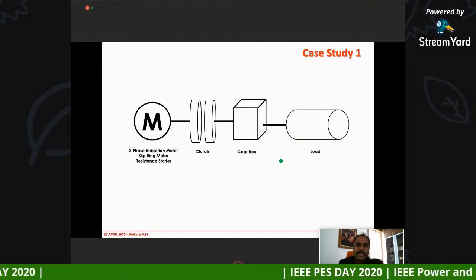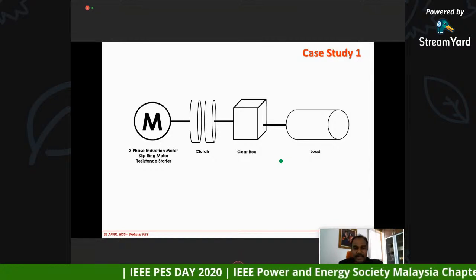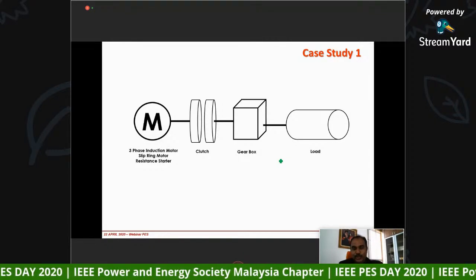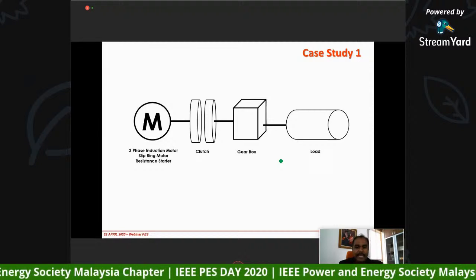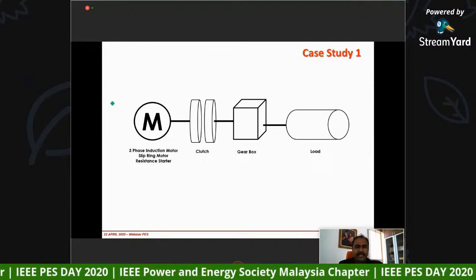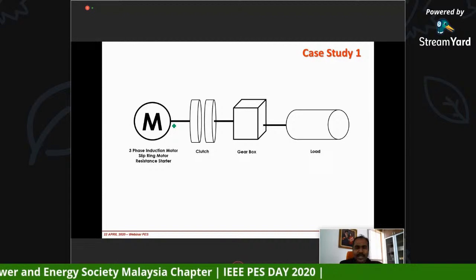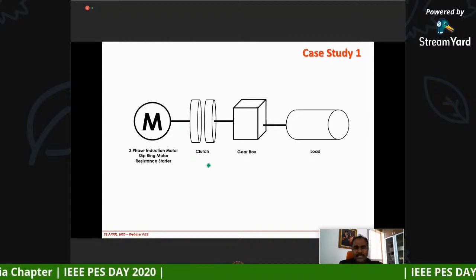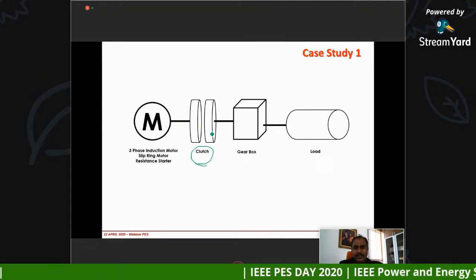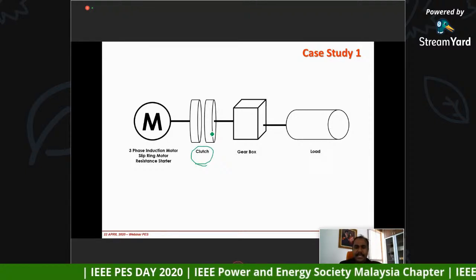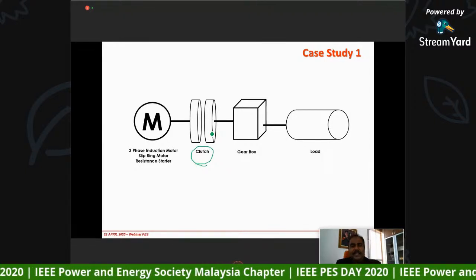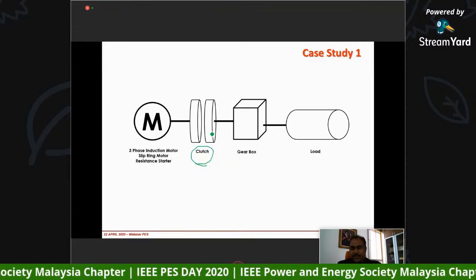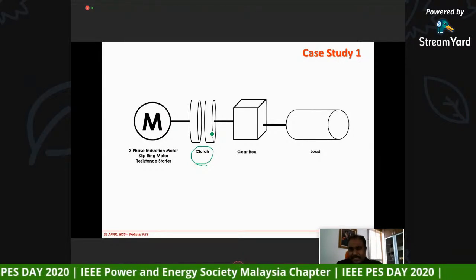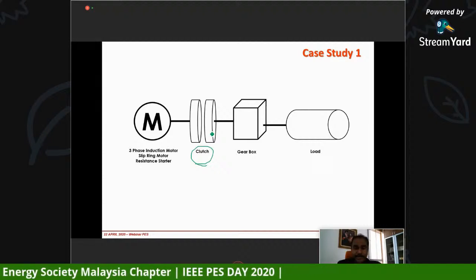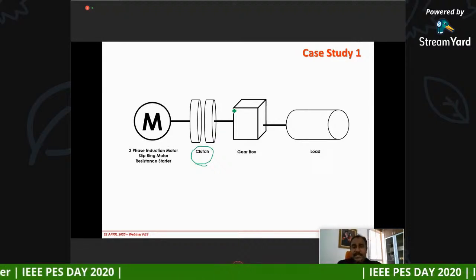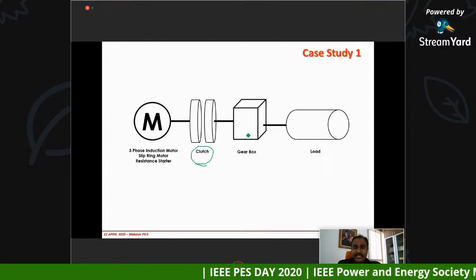So this is actually a real system that we have worked on, and it's a good example to show you the do's and don'ts. Now look at this motor. This is actually an over-200-kilowatt motor, a huge motor, and it is connected to a clutch. As you can see, there's a clutch here. That means it can engage and disengage. Normally when the motor starts, the clutch is always disengaged, so the motor starts with more or less no load. Then you have a gearbox, then of course the load. The load is connected to the gearbox.